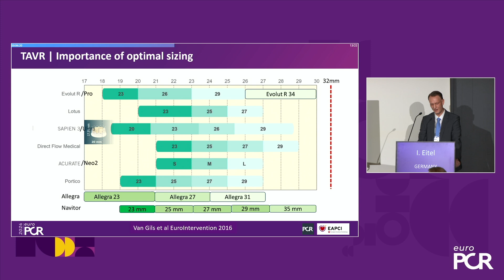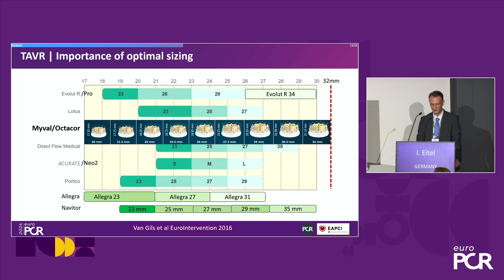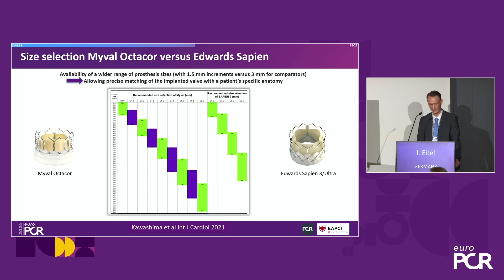You see the different TAVR manufacturers, and now we have the option with the Myval Octacor. We have 9 sizes, starting from 20 up to 32, and there we don't have to make any more compromise like under- or oversizing or putting more fluid in the balloons. Now we can really choose the optimal size for the individual anatomy, and this wider range allows a precise matching of the implanted valve. We have just 1.5 millimeter increments, as compared to 4 sizes, for example, for the Edwards Sapien with 3 millimeter increments, so you have a really fine calibration.